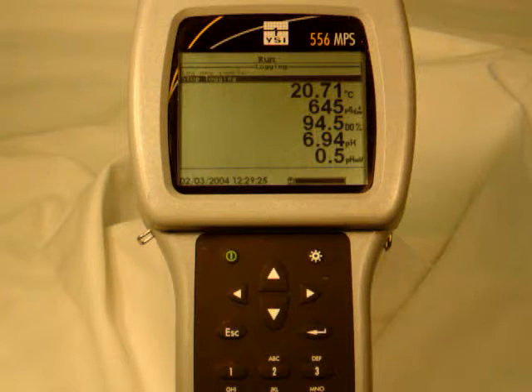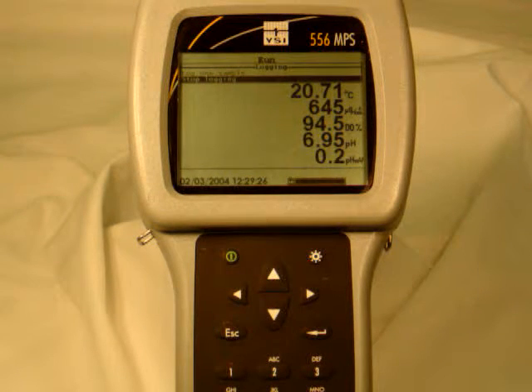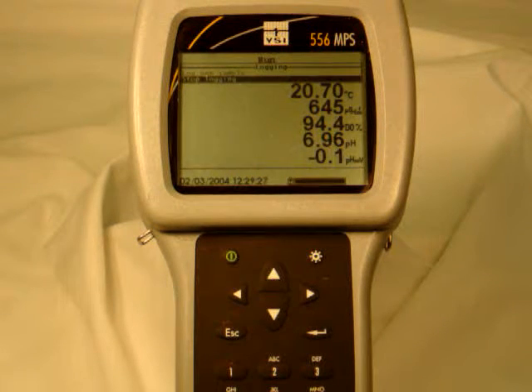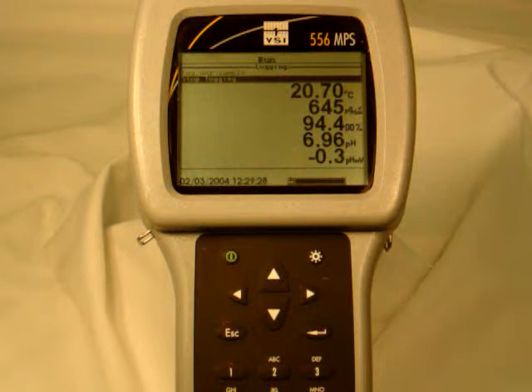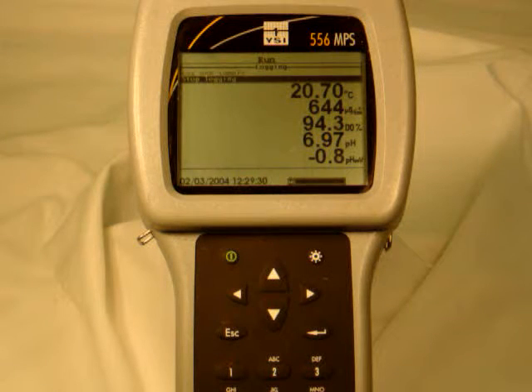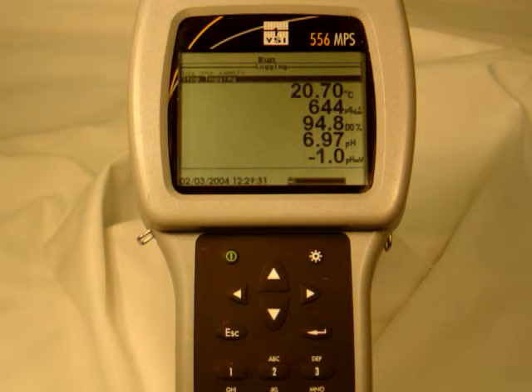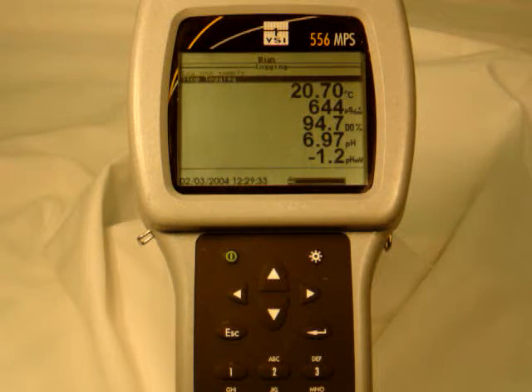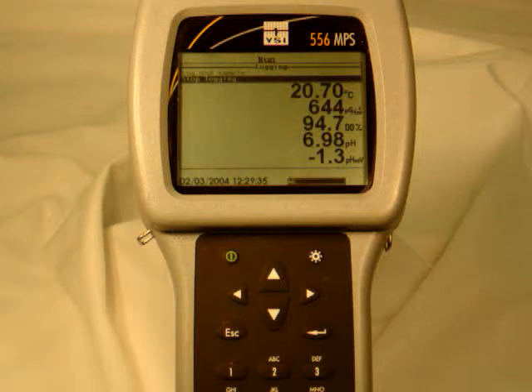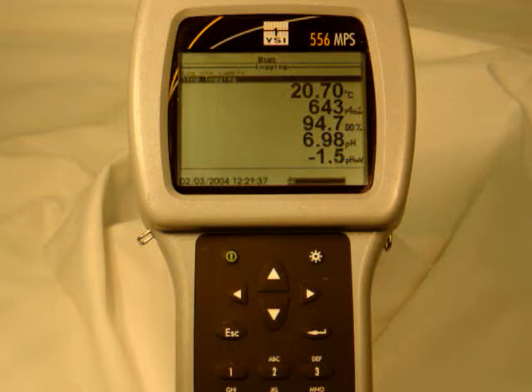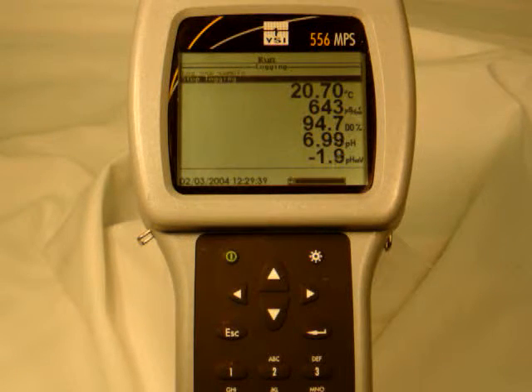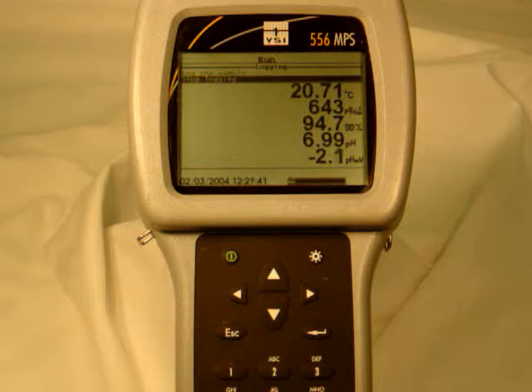Ground loops is what I was going to tell you. That was one of the big issues with pH sensors. Surface area. And there's tiny surface area on these pH sensors relatively. And, you know, the reference. Those are things that will affect the performance of the pH sensor.